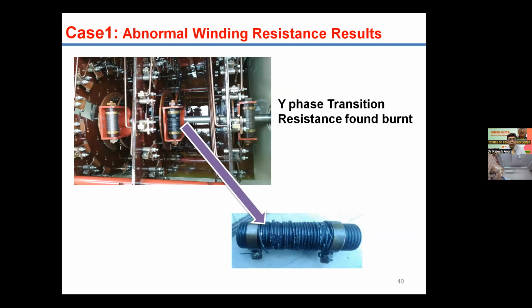But we were seeing the effect of it also when we were measuring the static resistance. Why it was so was that due to some misalignment in the YB phase, this pole arm, this resistance was not getting disconnected after changing the tap position. So it was also feeding the load current for which it was not designed. And due to this, it got damaged.